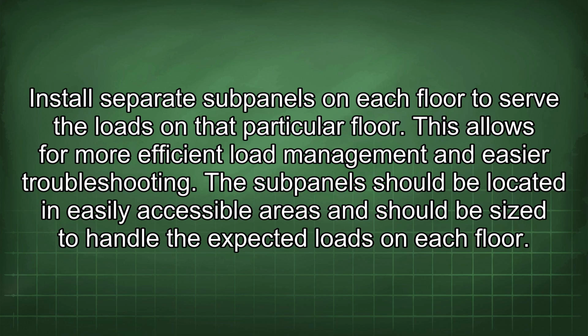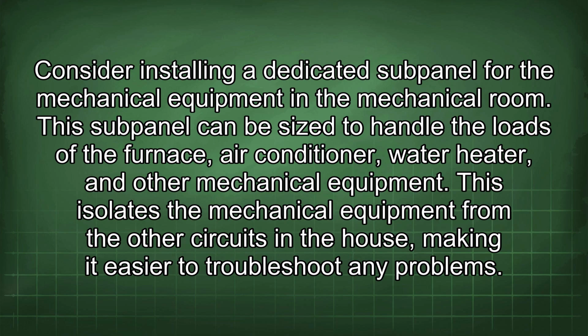The subpanels should be located in easily accessible areas and should be sized to handle the expected loads on each floor. Consider installing a dedicated subpanel for the mechanical equipment in the mechanical room. This subpanel can be sized to handle the loads of the furnace, air conditioner, water heater, and other mechanical equipment. This isolates the mechanical equipment from the other circuits in the house, making it easier to troubleshoot any problems.